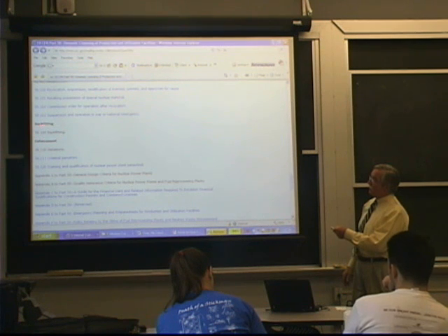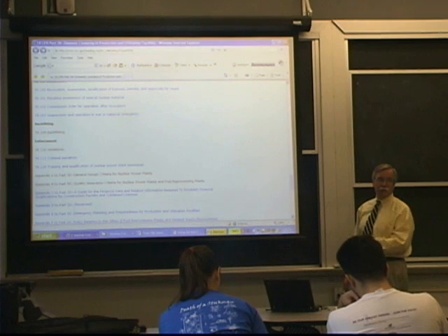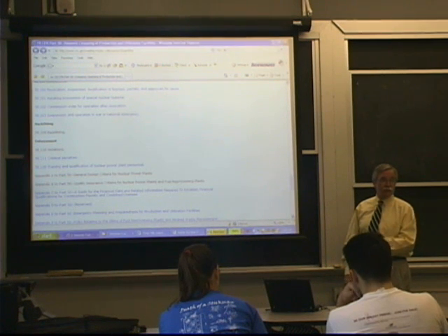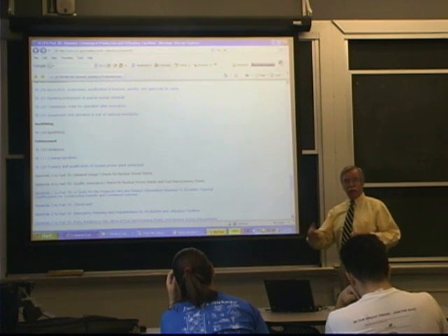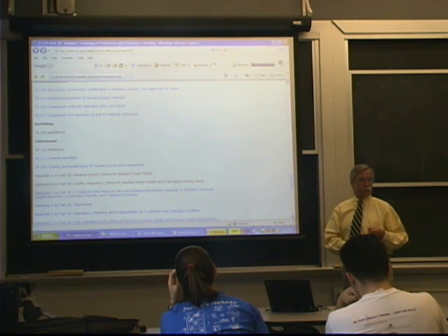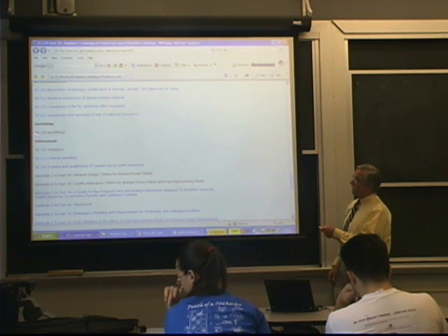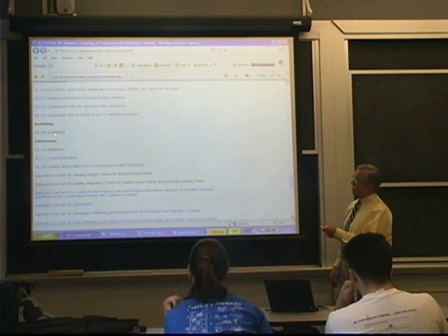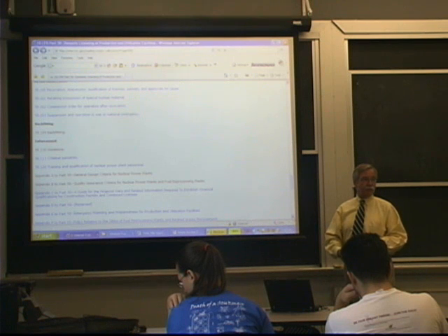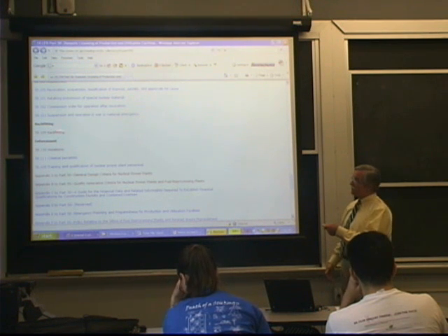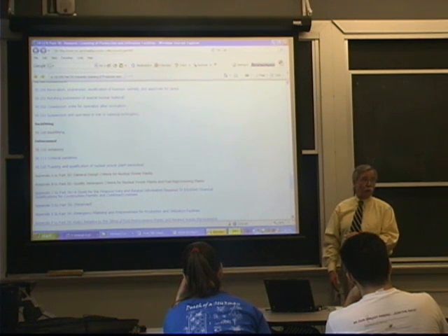One of the things, I remember one of my employees at Yankee worked very hard to get in this 50.109 rule. It's backfitting. The NRC can, at any time they want to, make you change your design based on their perception of risk and value. We got a rule in place called the backfit rule that said you can't just do this arbitrarily. You have to show cost-benefit value for that change. And this rule protects against arbitrary changes in design or requirements, backfit.